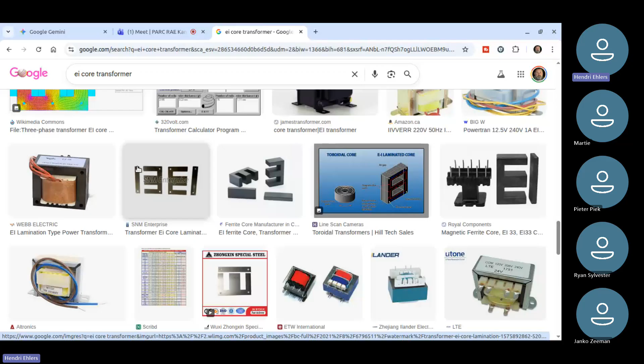This is what they call an IE or EI core, the E and the I. The reason why they've broken this up is that if you have this continuous, you actually create another circuit over here. You induce a magnetic field, which then cuts through this section, and you have a current over there as well: eddy currents. And that is the losses. After a lot of research, they realized that if they break it up into a bunch of loose plates, it's much more efficient than a solid piece of steel.